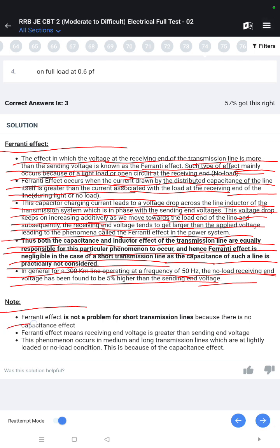In general, for a 300 kilometer line operating at a frequency of 50 Hz, the no-load receiving end voltage has been found to be 5% higher than the sending end voltage. Note: Ferranti effect is not a problem for short transmission line because there is no capacitance effect. Ferranti effect means receiving end voltage is greater than sending end voltage. This phenomena occurs in medium and long transmission lines which are at lightly loaded or no load condition. This is because of the capacitance effect.